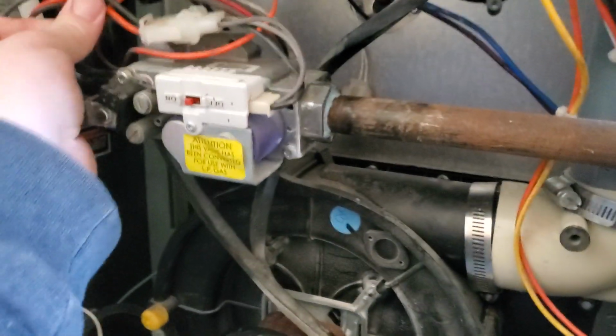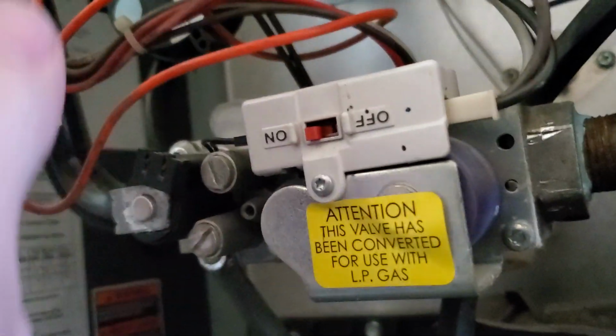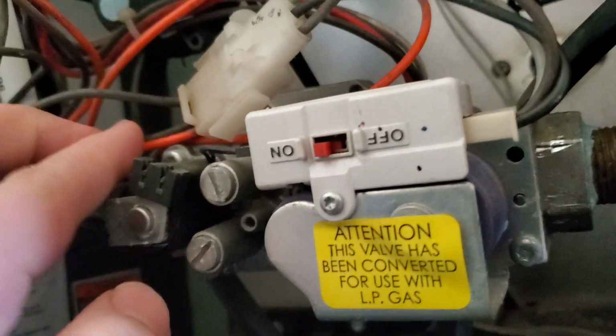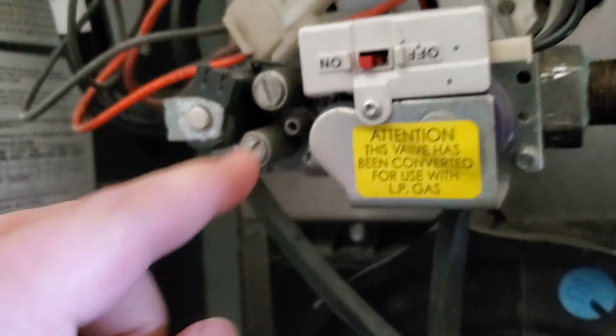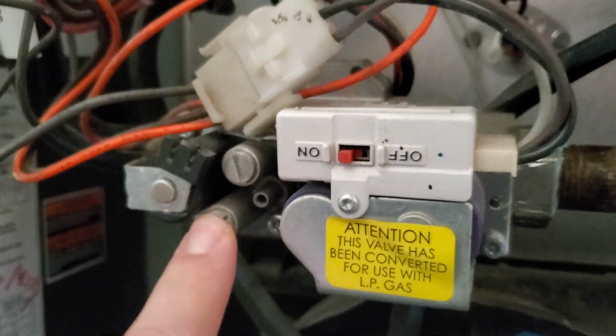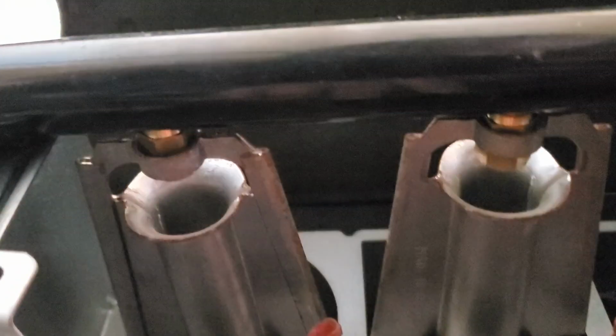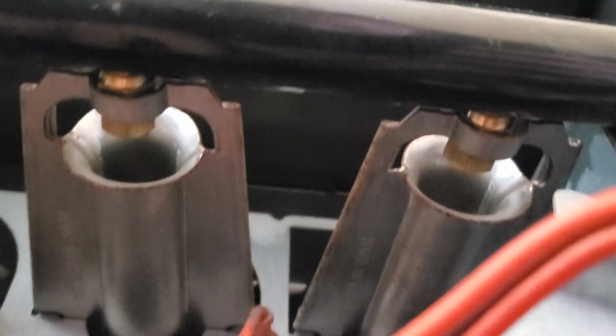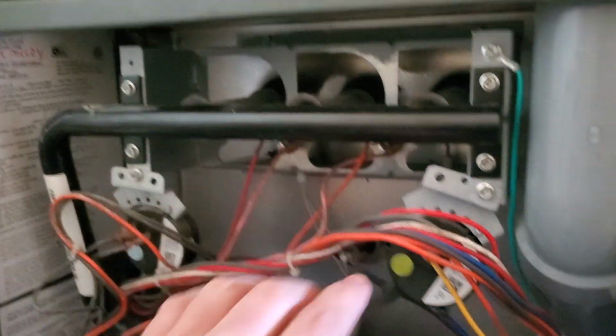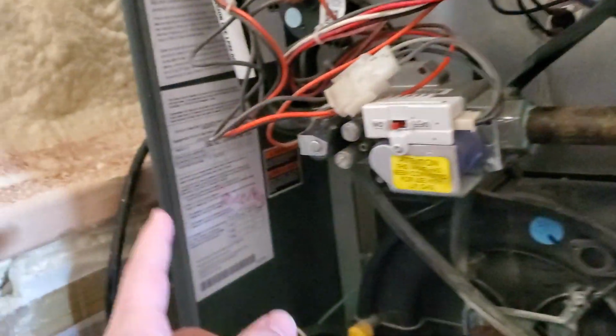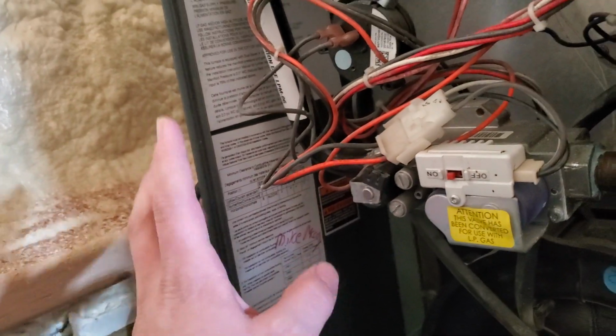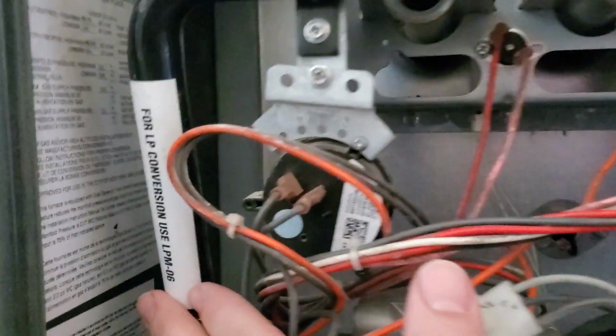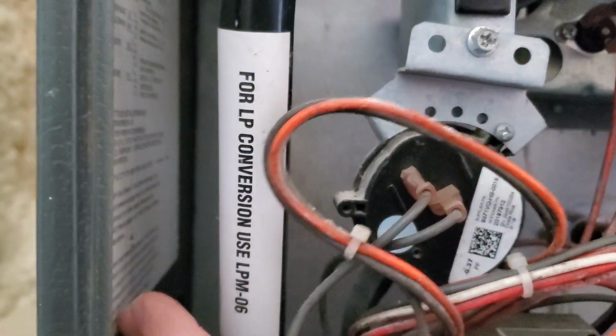So with a propane conversion, I'm just going to tell you what it involves. There's a couple of springs inside here. This is a two-stage furnace, so it has two springs. Sometimes you'll replace both of those springs, but if it just has one cap like this, you just need a single spring to convert it from natural gas to propane, and then you'll need different orifices. These little brass orifices you see up in there are a different size for natural gas than they are for propane. So you need a conversion kit to convert whatever model furnace that you have. Look at the model number, look it up. You should be able to order a propane conversion kit, and then you will be good to go once you do get it converted.